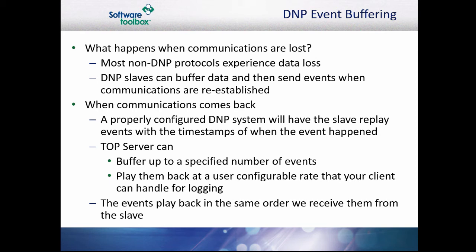Once we have good communications, a properly configured DNP3 slave that fully supports the DNP3 protocol specification will send the events with timestamps to the master in sequence, with oldest timestamps sent first. The TOP Server can then buffer these events up to its configurable maximum per tag and play these out to the client application at a user-configurable playback rate. Please note that we replay these events in the order we receive them from the slave, so if the slave provides the events in the correct first-in, first-out timestamp order, the events will be sent to the client in the same order.